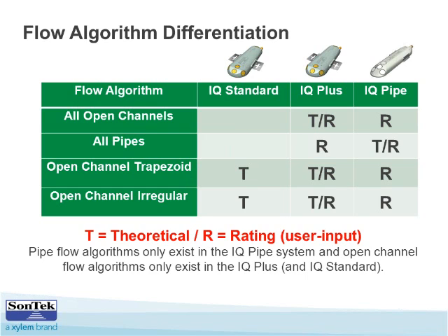Proprietary flow algorithms are specific to the type of instrument you buy. If you buy an IQ Plus, the proprietary flow algorithms are for open channels, though you can do your own rating or velocity indexing for a pipe with it. Similarly, if you have an IQ Pipe, the proprietary flow algorithms are for a pipe. You can put it in an open channel, but then you'll need to rely on your own indexing or rating to turn velocity into flow. Hopefully that was clear, but let us know if you have questions about where each one should be installed.